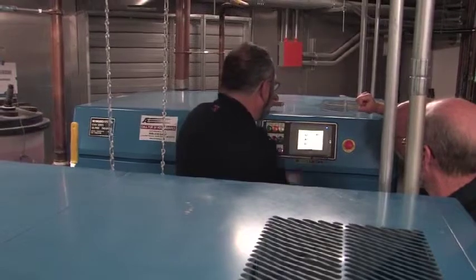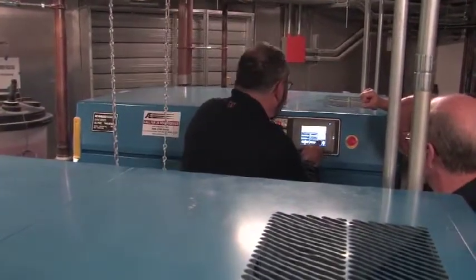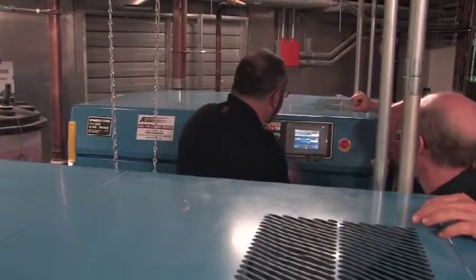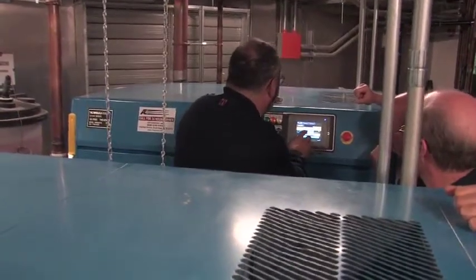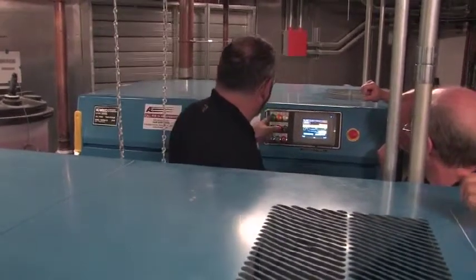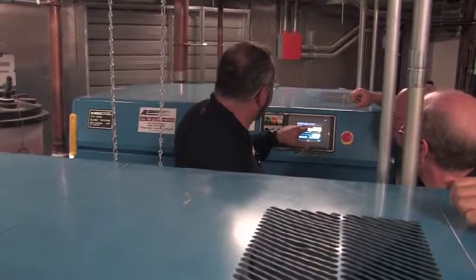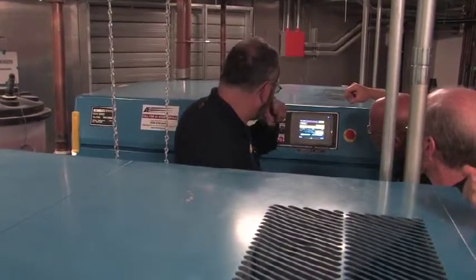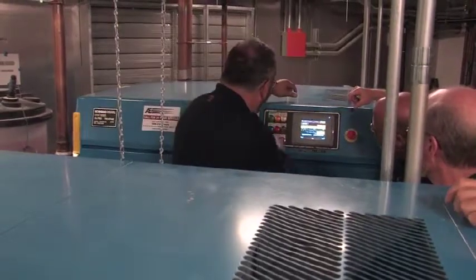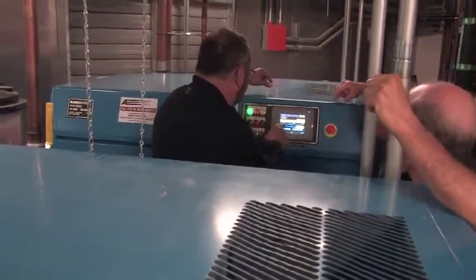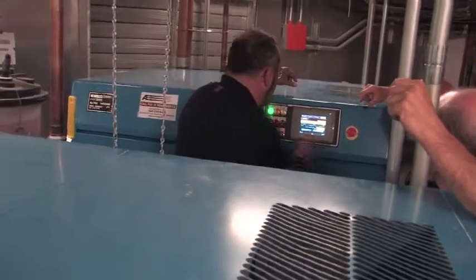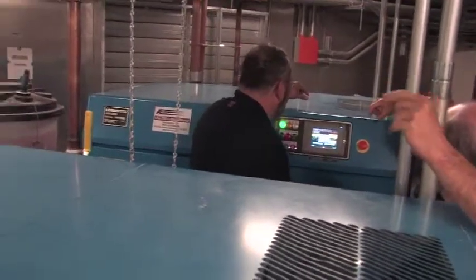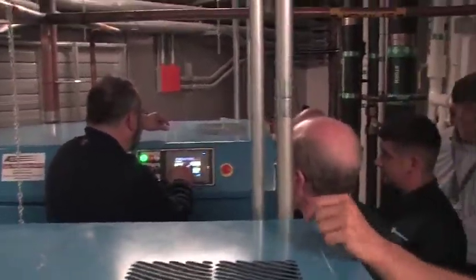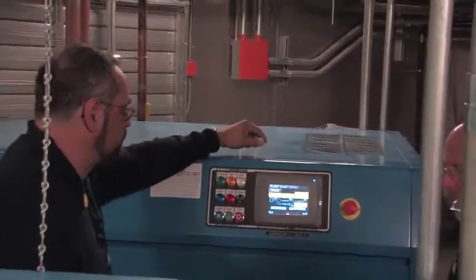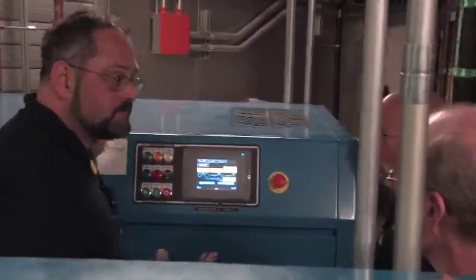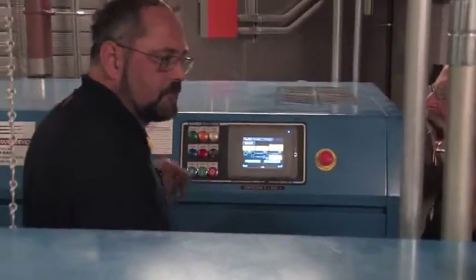As long as the sequencer is up and running, right? Well, here's the interesting thing. If we put it back in the sequencer, I'm going to put it back in remote. Now, it's blinking. Now notice what it says right here, this red line that comes up. In order to enable the sequencer, I actually have to hit the start button. That's interesting. So what you're doing right there isn't enough. You also have to tell it. That's almost like clicking OK on a mouse. Yep, you're confirming it. So if you walk by and this light's blinking, you've got to hit the start button to make sure it puts it back on the sequencer.